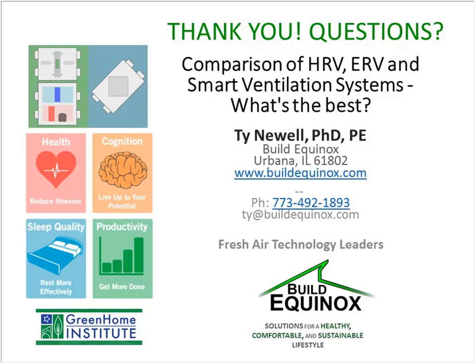But the other aspect relative to your question is that maybe 20 CFM is okay if you're in your house 24 hours a day, but there's a lot of people in the house for a certain part of the day and then not so many for another part of the day, and the ventilator just keeps continuously running, isn't bringing in enough fresh air when it's needed, and then isn't closing down the ventilation level when it's not needed. Those two aspects are what a smart ventilator can address: supplying as needed based on the activity level and number of people and when they're there. It just automatically takes care of the scheduling.